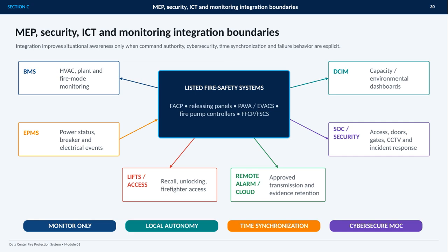The BMS monitors HVAC, plant conditions, and fire mode status. The EPMS reports power status, breaker positions, and electrical events, while the DCIM presents capacity and environmental information. Security operations add access control, doors, gates, CCTV, and incident response. Lift systems support recall, unlocking, and firefighter access. Approved remote alarm or cloud connections may extend visibility and preserve evidence, but they must be controlled. Across all these interfaces, the design should distinguish monitor-only points from commands. It should preserve local autonomy, maintain accurate time synchronization, and apply a cybersecurity management of change process. These boundaries determine what happens during normal operation, communication loss, or a conflicting command.